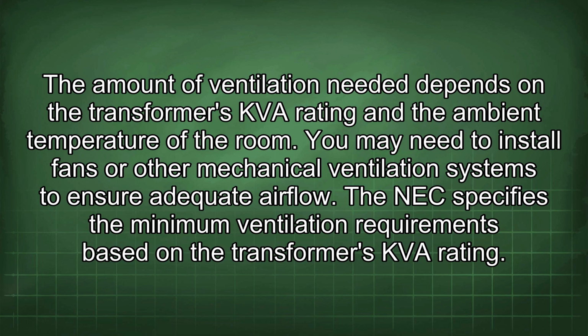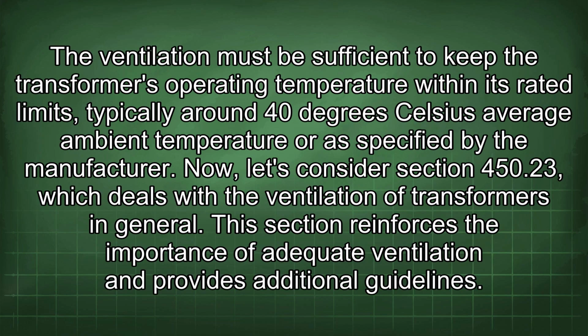The NEC specifies the minimum ventilation requirements based on the transformer's kVA rating. The ventilation must be sufficient to keep the transformer's operating temperature within its rated limits, typically around 40 degrees Celsius average ambient temperature, or as specified by the manufacturer. Now let's consider section 450.23, which deals with the ventilation of transformers in general. This section reinforces the importance of adequate ventilation and provides additional guidelines.